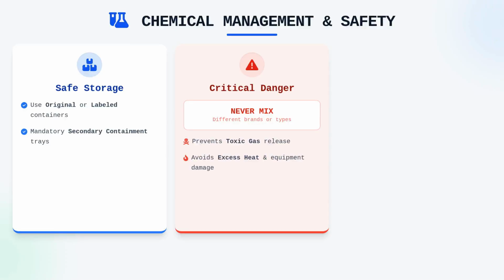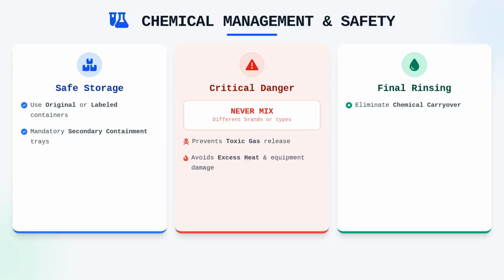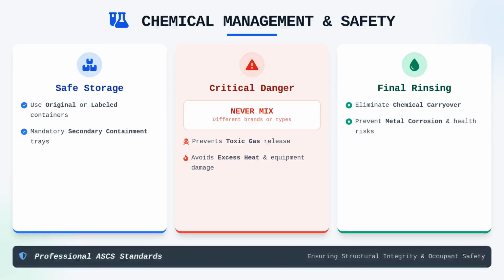Once the cleaning process is complete, thorough rinsing is the most critical step to prevent chemical carryover into the airstream. Any residue left on the fins will eventually become airborne once the air handler is turned back on, potentially causing health issues for occupants or leading to the slow deterioration of the metal due to prolonged chemical exposure. By adhering to these structured protocols, you ensure that the system remains both clean and structurally sound, fulfilling the professional standards expected of an ASCS.